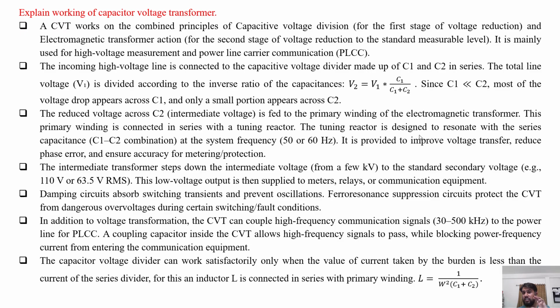Since the value of C1 is very small as compared to C2, most of the voltage drop appears across the capacitor C1. So only a small portion appears across the secondary capacitor C2. Now the reduced voltage across C2, that is the intermediate voltage, is fed to the primary of the electromagnetic transformer. This primary winding is connected in series with a tuning reactor connected in the circuit.